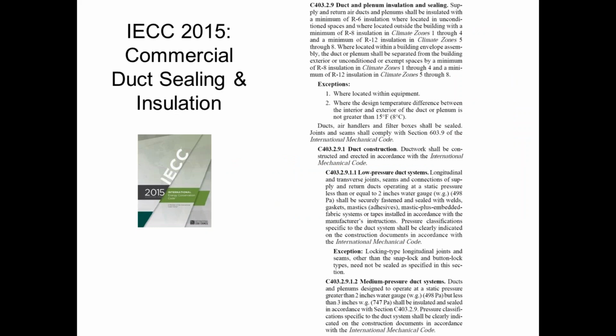The code does require duct sealing and duct insulation. So first off, your supply and return ducts and plenums need to be insulated to R6 when they're in unconditioned spaces. And then if they're outdoors, for our climate zone, they've got to be R12. That's a pretty big increase. So if you have ductwork that's running outside, for example a rooftop unit with side discharge, horizontal discharge into the side of a building, that's going to have R12 insulation. So plan that ductwork being much larger because the insulation is probably going to be on the inside.